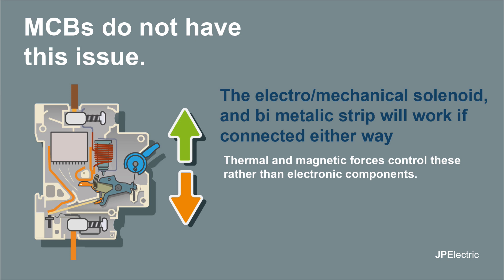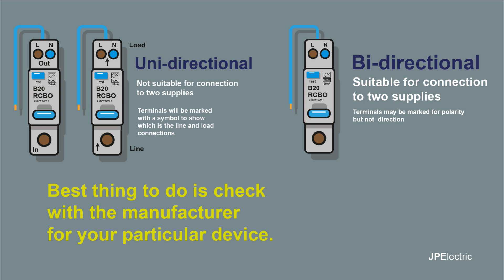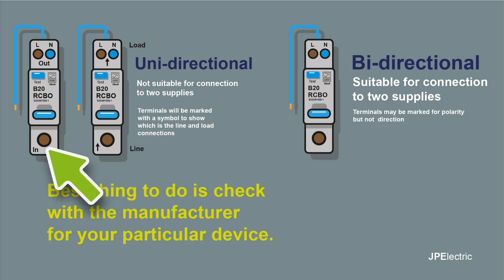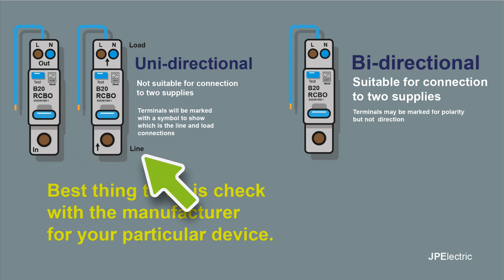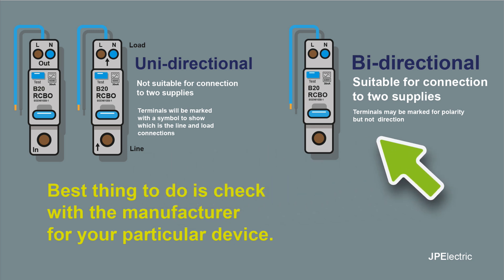MCBs generally don't seem to suffer from this issue, because they haven't got any electronic components which can fail. The solenoid and the bimetallic strip will work if connected either way. To identify which device is which: unidirectional devices have some indication of the flow of power — it'll say 'in' and 'out', or 'line' and 'load', so you know it's not suitable for two connections. A bi-directional device will not specify which is in and out or line and load, or have an arrow showing direction. You might get markings for polarity, but the best thing to do is check with the manufacturer for your particular device, because the markings may not be clear or obvious.